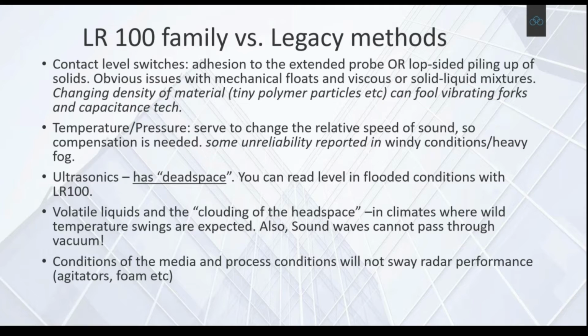Even with vibrating forks and capacitance technologies, you will experience issues with dense material. If it's granular or small, it could change because of humidity or moisture, and it compacts around the edges of that vibrating fork's prong, usually a single prong, and that can fool it - it could tell it to switch on when in fact it's not in the bulk solid itself.